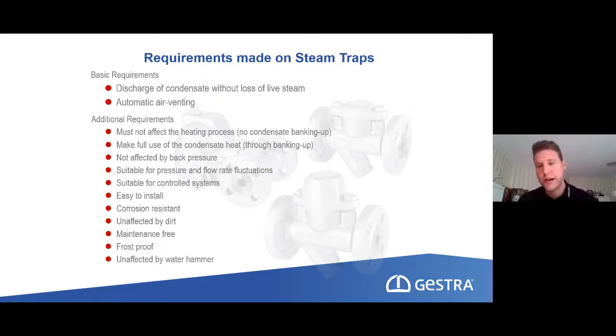And that tells us that a steam trap has to be able to handle different amounts of condensate and also different pressures. When I start up the system, the pressure in the beginning is rather low, but it's increasing, and they have to control it more or less. Some steam traps can do that very well, and some might have problems with that, but we will see the difference here. What should also be very nice, especially nowadays, is the easy-to-install requirement. In the past, it was very hard with the design of older kinds of steam traps to install them in the pipeline, because of the design of the body and so on. Today we have changed a lot in the design so that it's very easy to exchange them, and this will rapidly decrease the maintenance time that I need to exchange one of the steam traps. So the downtime of the system is much lower.